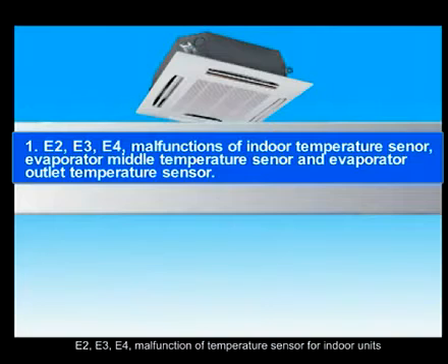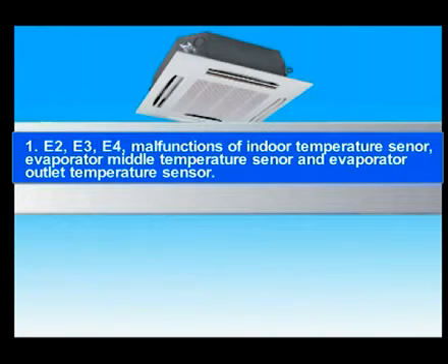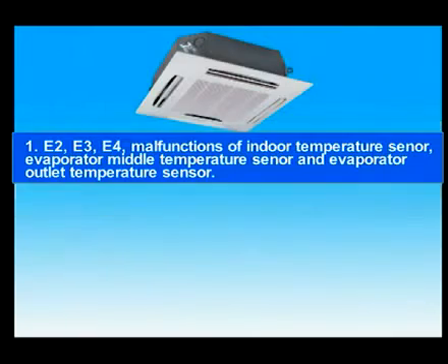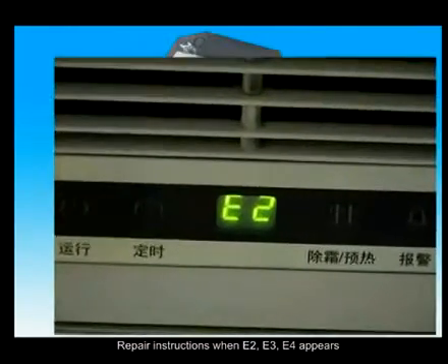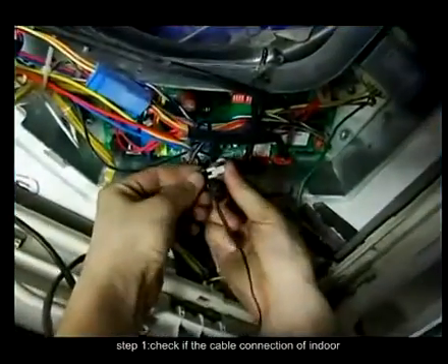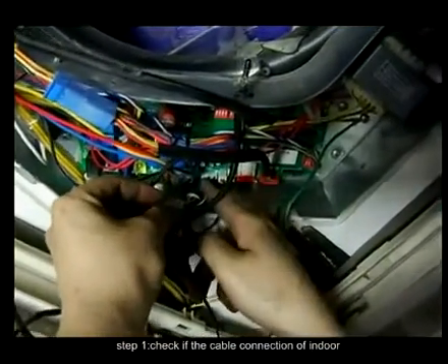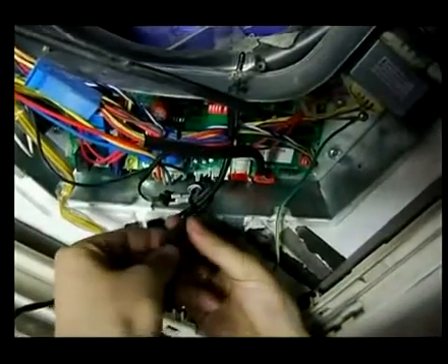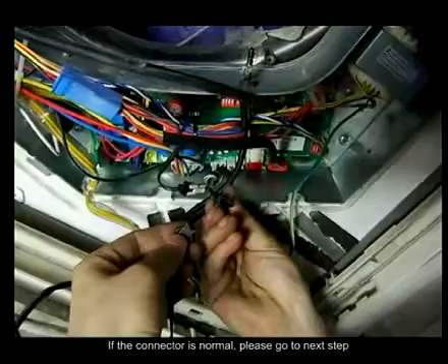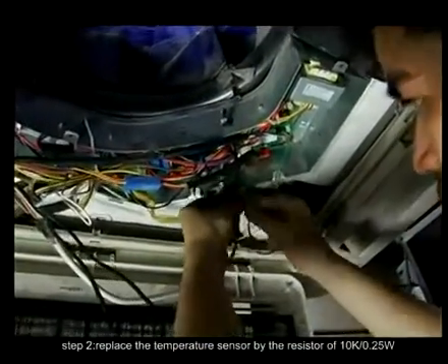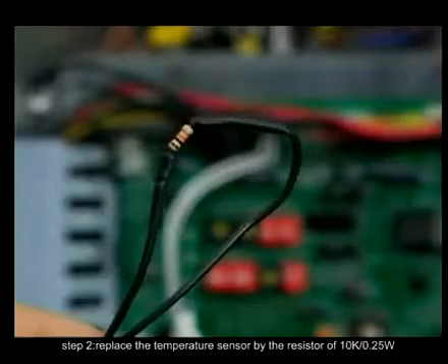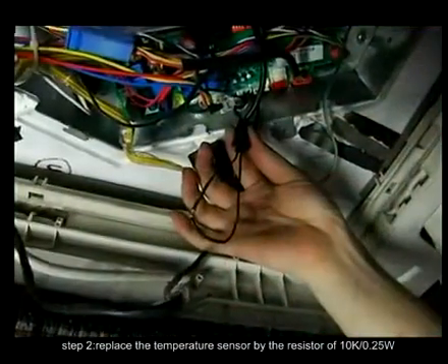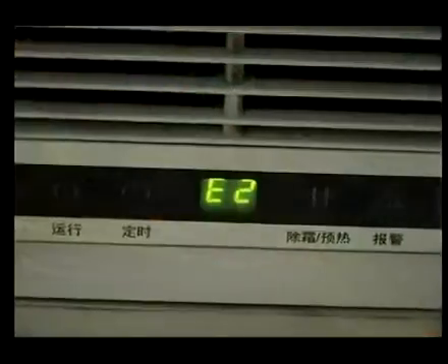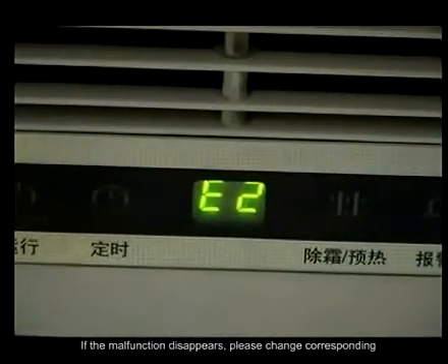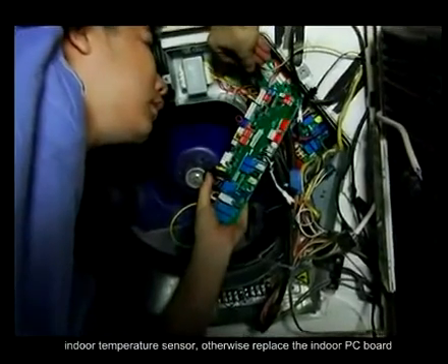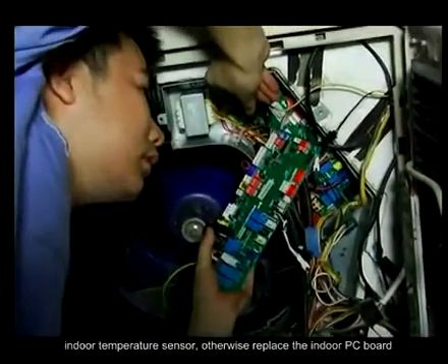E2, E3, E4, malfunction of temperature sensor for indoor units. Repair instructions when E2, E3, E4 appears. Step 1. Check if the cable connection of the indoor temperature sensor is correct and reliable. If the connector is normal, please go to the next step. Step 2. Replace the temperature sensor with a 10K, 0.25 watt one. Then check if the malfunction disappears or not. If the malfunction disappears, please change the corresponding indoor temperature sensor. Otherwise, replace the indoor PC board.